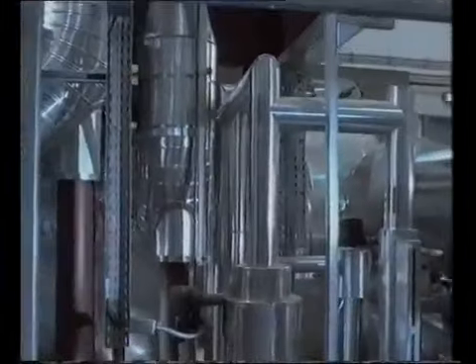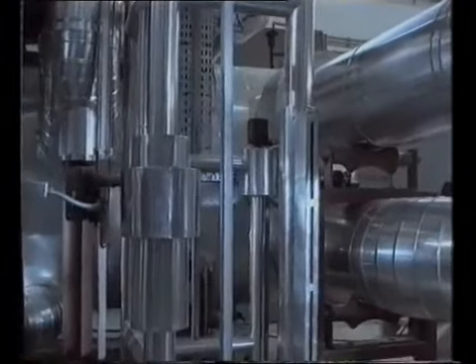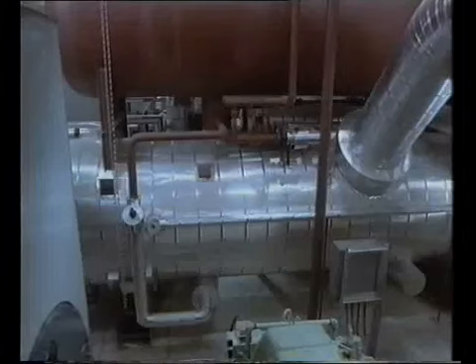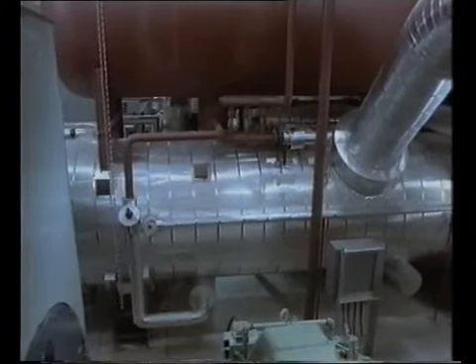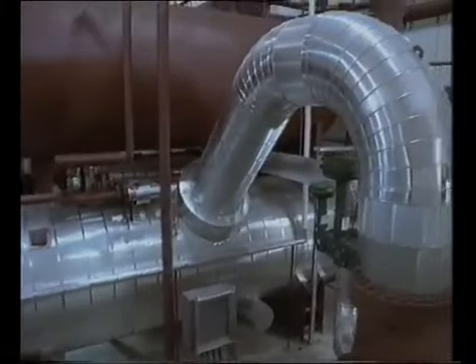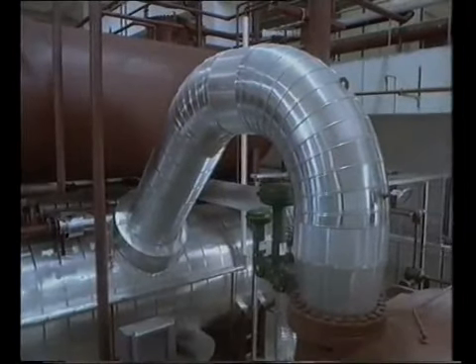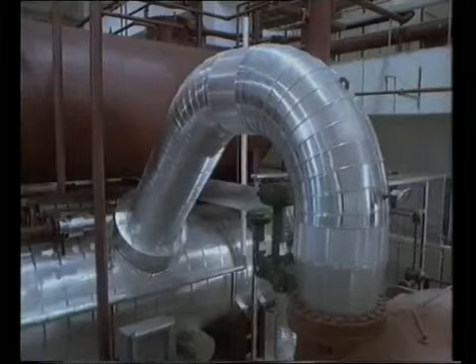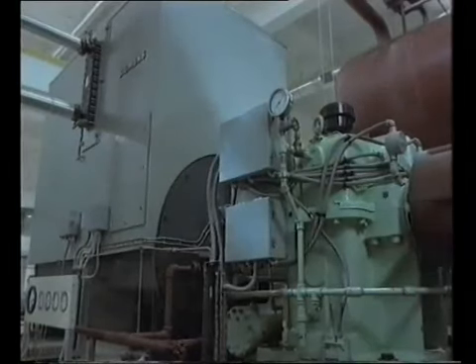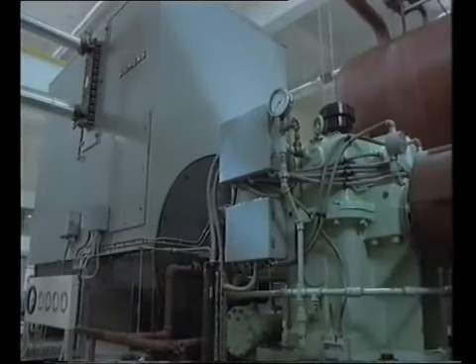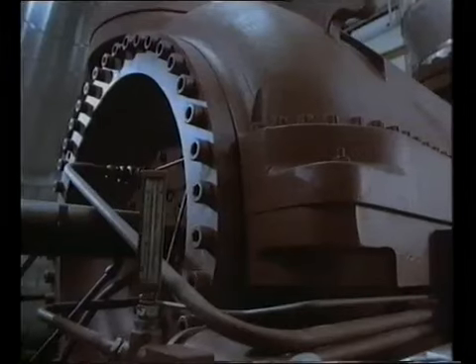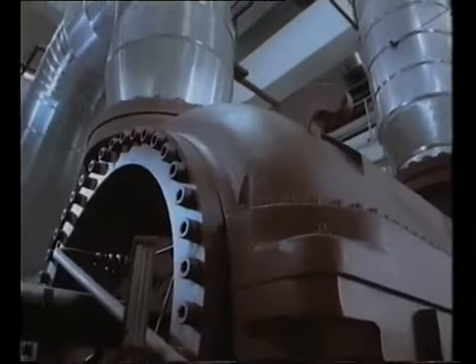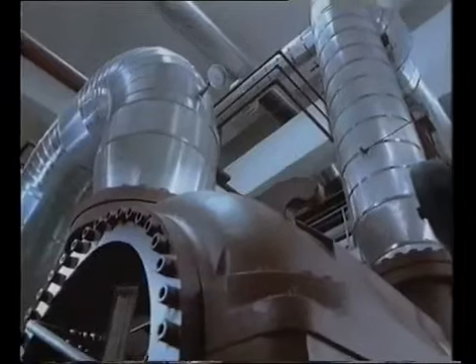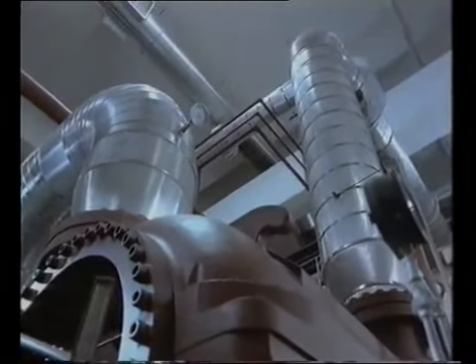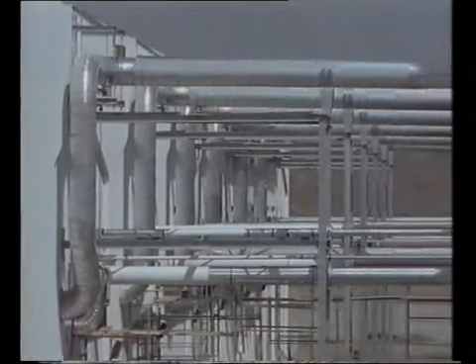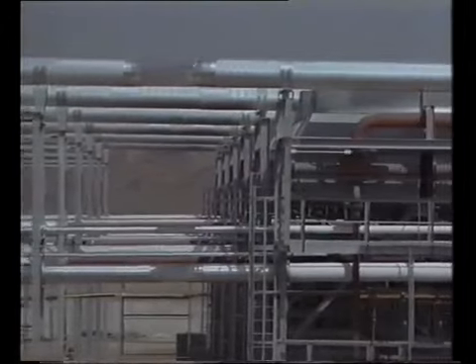The chilled water leaves the evaporator to go back to the Haram basement, whilst the gas needs to be turned back into a liquid so that the vapor compression cycle can continue. The gas passes into a centrifugal compressor. A 5,200 kilowatt electric motor and gearing drives the centrifuge, which compresses the refrigerant to 19 bar. This raises its temperature to 66 degrees centigrade. The gas is forced outside the chiller building in piping to the 6 condensers.